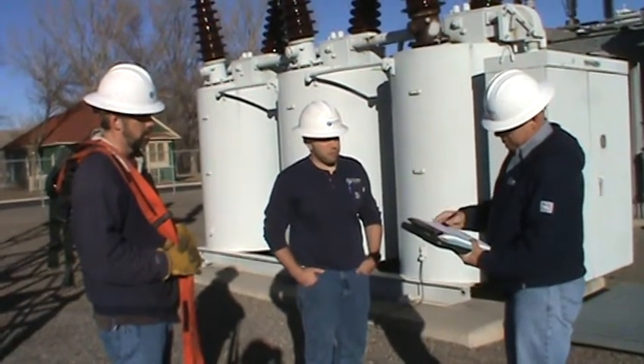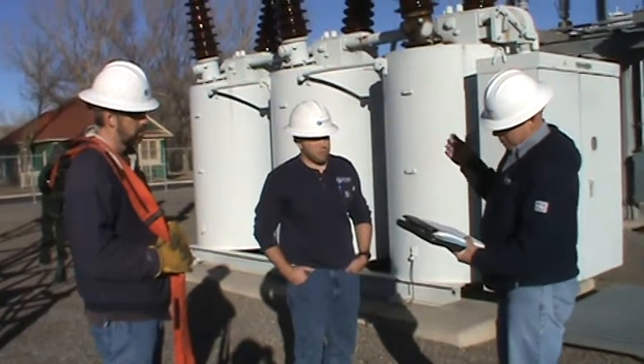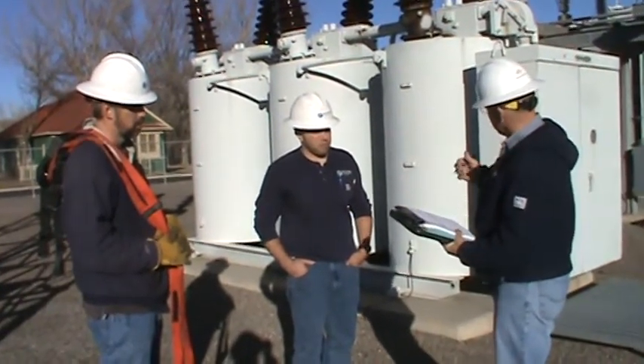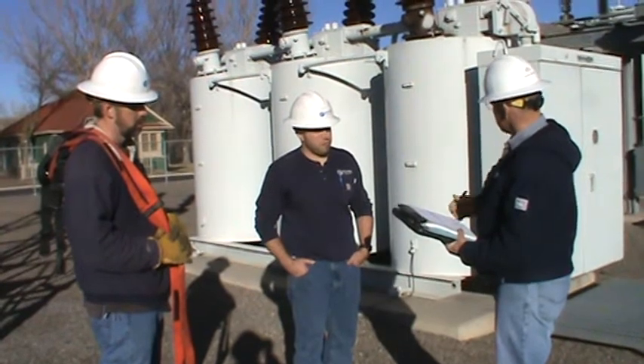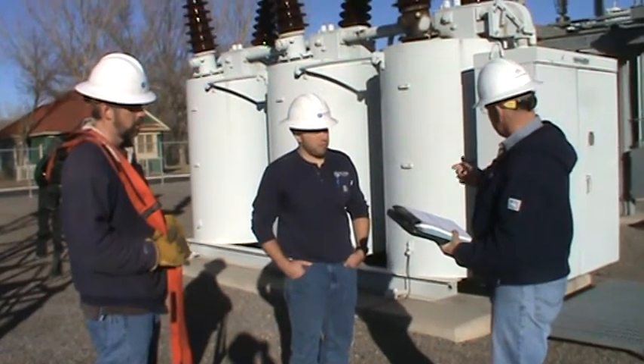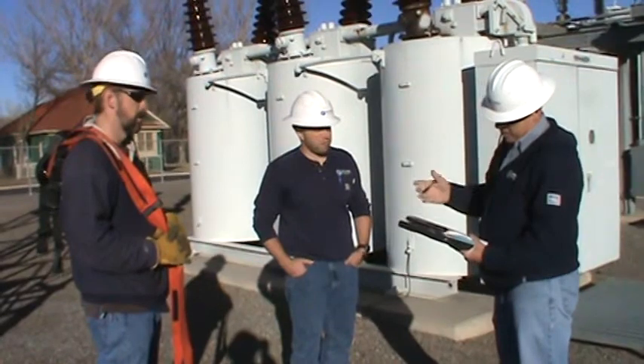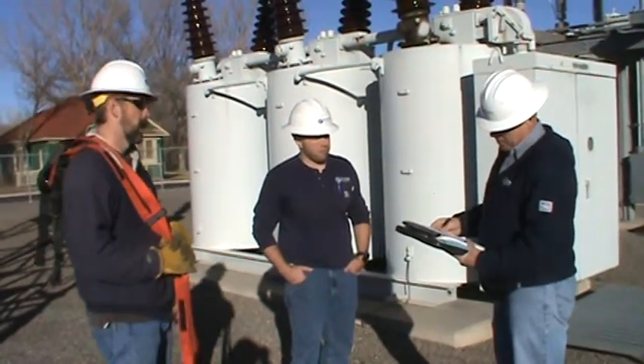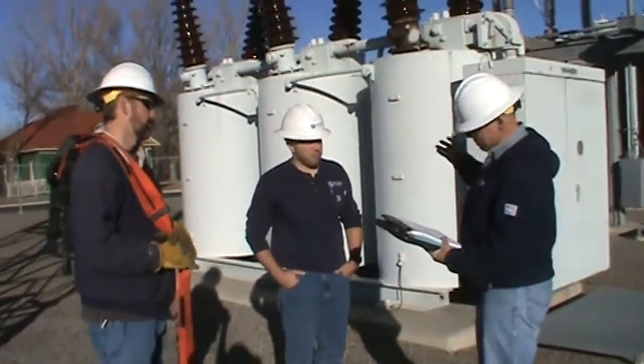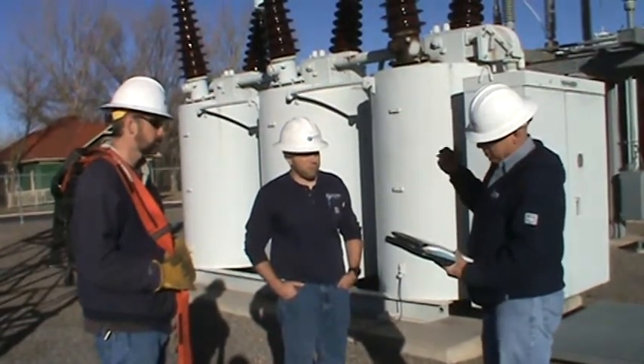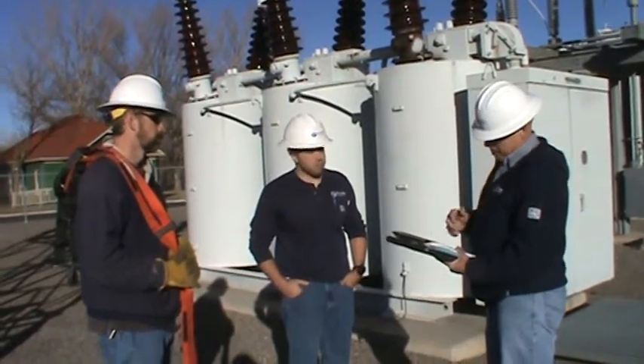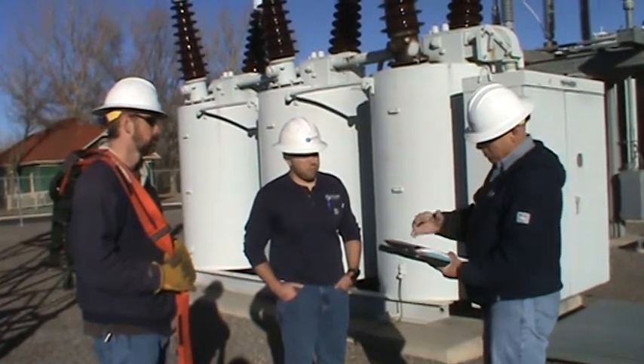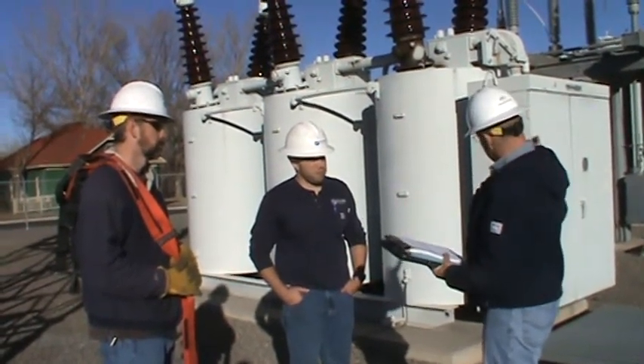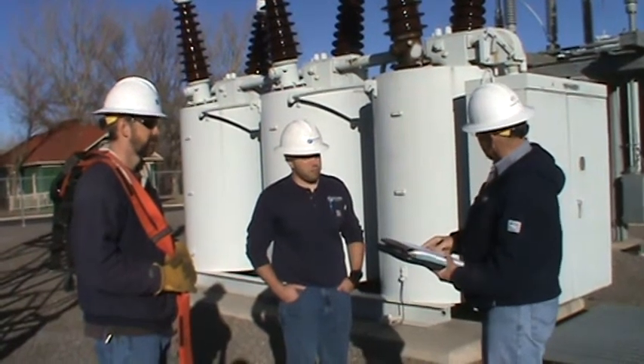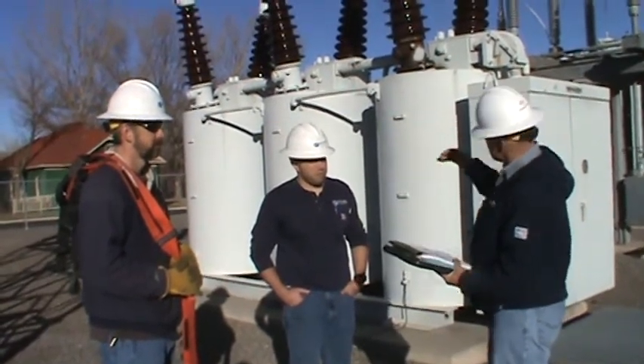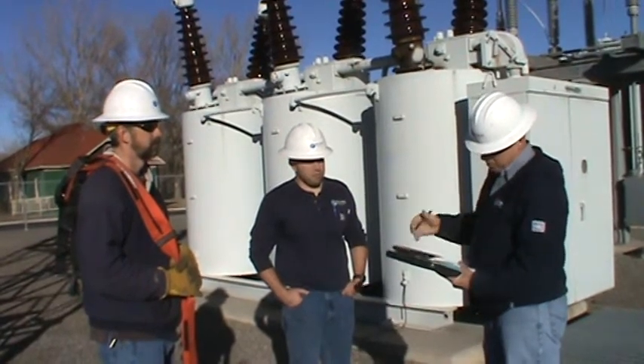And on the confined space end of it, gentlemen, at that time, when we're done with all of our electrical testing, we pull all the oil out of the breaker. We're going to be doing, use a stop work. And at that time, we'll get our confined space permit out and we will downgrade this to a non-permit required confined space. JD will get the air sniffer, crack all 3 doors, monitor the air, and we'll fill out the permit at that time. And at that time, gentlemen, like I said, we'll go over our confined space permit and make sure we do all of our checklists on our stored energy. And we've got all the hazard controls in place, shorten out the bushings and all that stuff on top before we go inside the breaker.